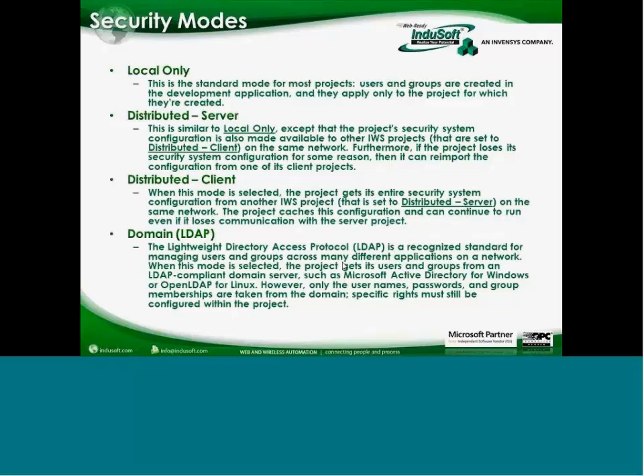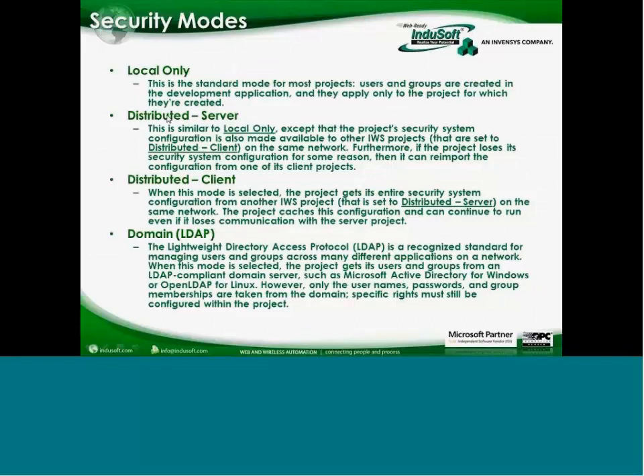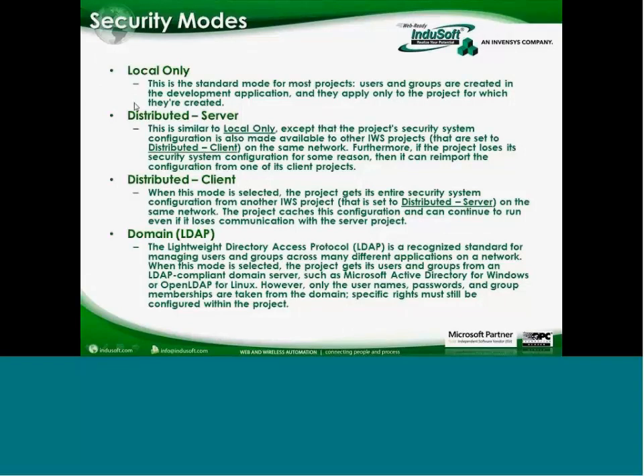Indusoft Web Studio has four different security modes. The local-only security mode is our own built-in system, and for most HMI projects it's the type most people will choose. The distributed server and distributed client modes work hand-in-hand — you have a server that hosts the security system and clients that authenticate against it. If the server is offline, clients have their own cached copies. If you have multiple Indusoft Web Studio workstations, you'd typically have one server and multiple clients.